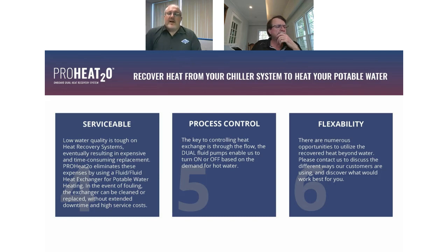On the process control side, the key to controlling that heat exchange is through the flow. Our dual fluid pumps enable us to turn on and off based on the demand for hot water, and that gives us great flexibility. There are numerous opportunities to utilize the recovered heat beyond the water, and you can get in touch with us and we can talk about ways that you can move that heat into other parts of your system and utilize it for things other than just your hot water processes.